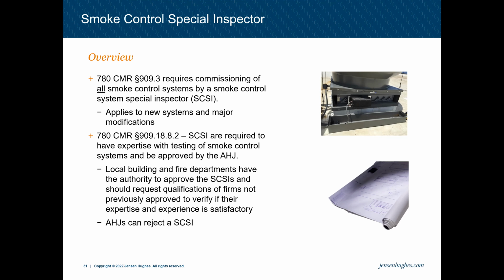And if there are questions, the special inspector should raise that to the installer and the design team to hopefully get a good solution. I personally do a lot of special inspections throughout the Northeast. I try to focus on the design documents as much as possible. And there's usually a gap between the design documents and what's being built, just because some stuff might not be detailed in the correct way, or might not be detailed completely in the design documents. I do try to flag that. And if I see something that doesn't comply with code, even if it isn't in the design documents, I will try to flag it to get ahead of stuff.